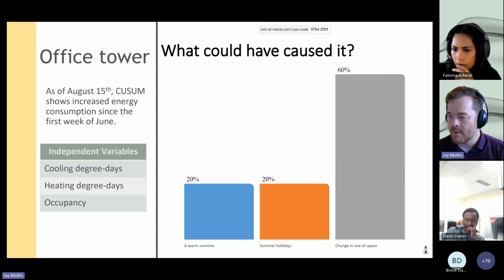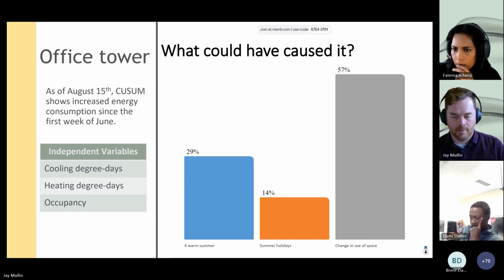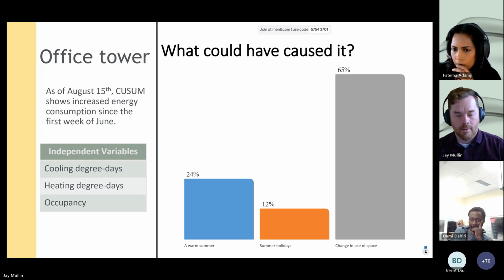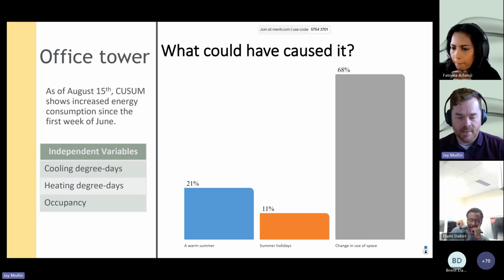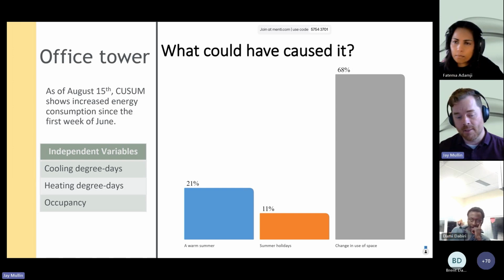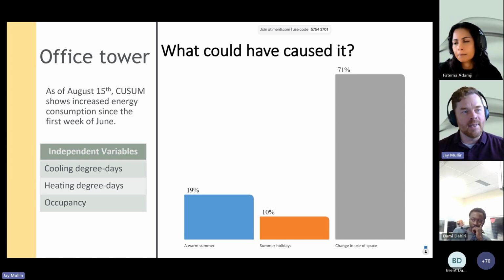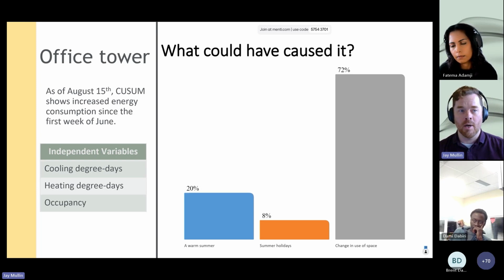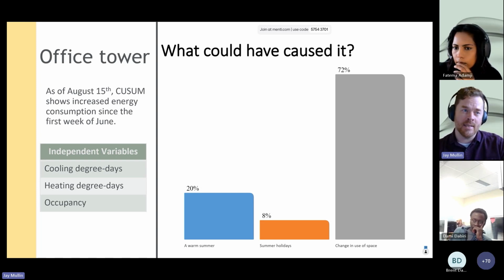All right, we're getting some answers in here, and it seems like change in use of space is dominating. So if I was looking at this model and saw this happening, I'd ask: is it because of a warm summer? Well, the model is already adjusting for cooling degree days, so that shouldn't show up in the CUSUM unless it was drastically different—like cooling degree days that had never shown up before, which the model doesn't know how to handle, or it causes the building to react differently. Those instances are relatively rare.